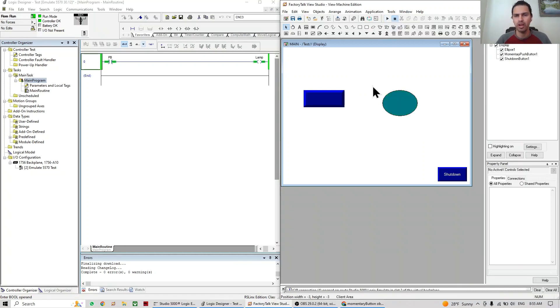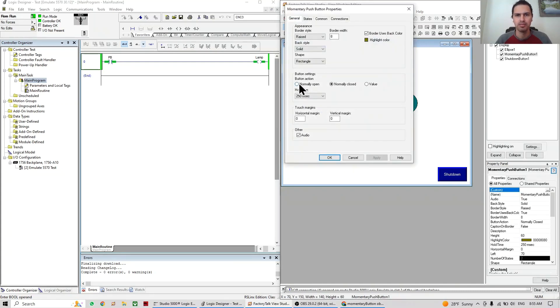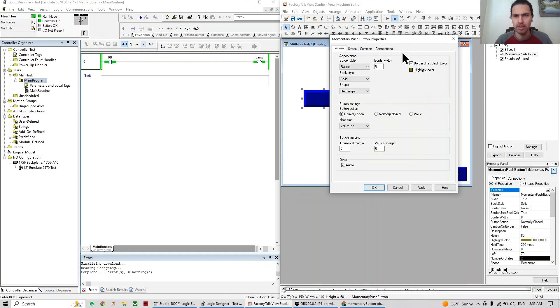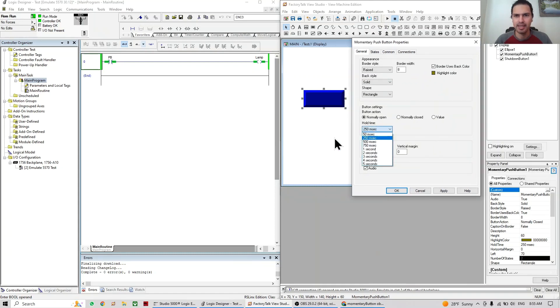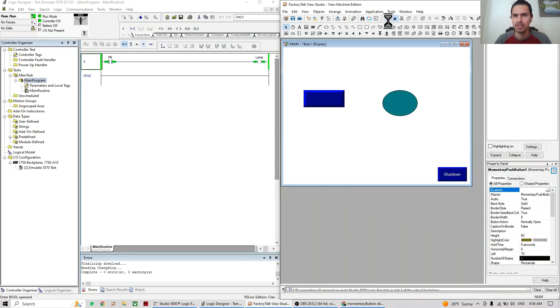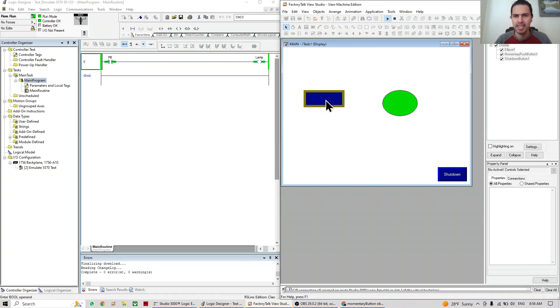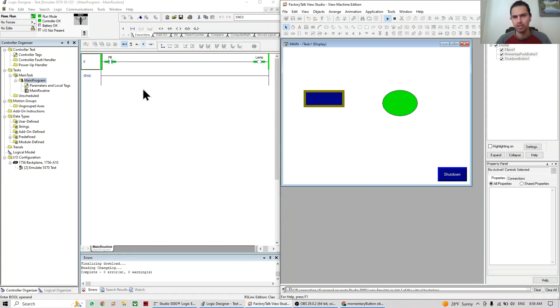It depends on your application, but most of the time it's going to be normally open. Hold time is the time that the HMI is going to hold the push button pushed. Right now it's 250 milliseconds; let's set it to the maximum just to see the difference. After applying, when I push the button it turns on, then I release the button and the push button stays on — it's still on for five seconds. In other words, the push button stays pushed for that amount of time.